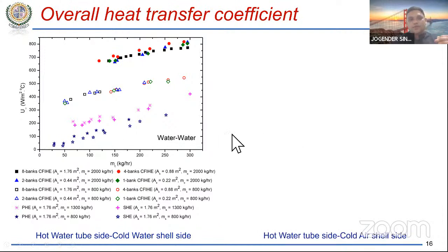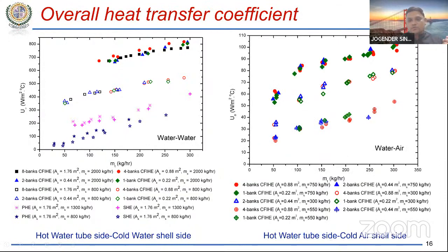Now, this experiment was for hot water in tube side and cold water in shell side. We repeated the same experiment for different arrangements of the fluids. So we took hot water on the tube side and cooled it down with air on the shell side, and there also we are getting very good results, in terms of the 2-bank heat exchanger, which provides a very similar heat transfer coefficient as provided by the 8-bank heat exchanger or 4-bank heat exchanger.